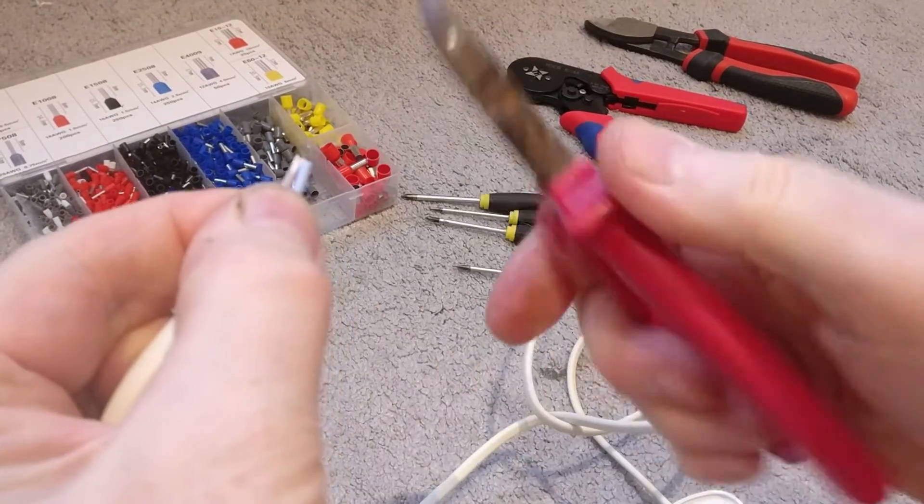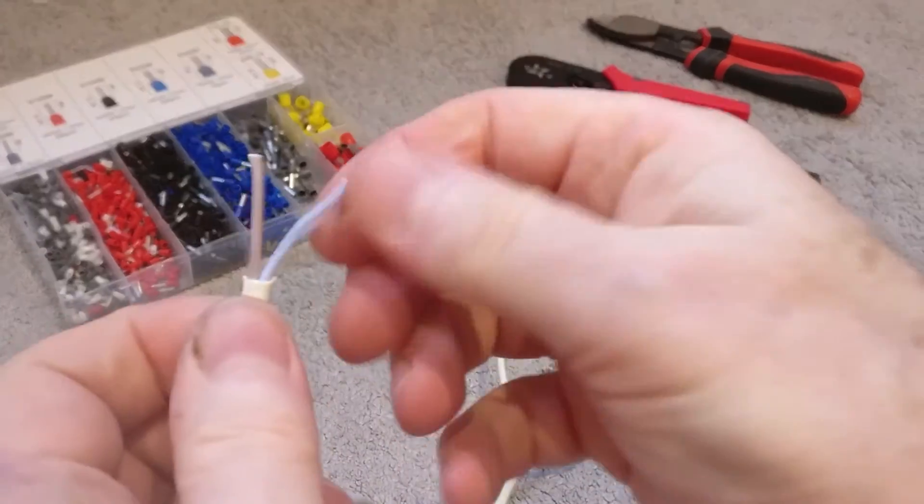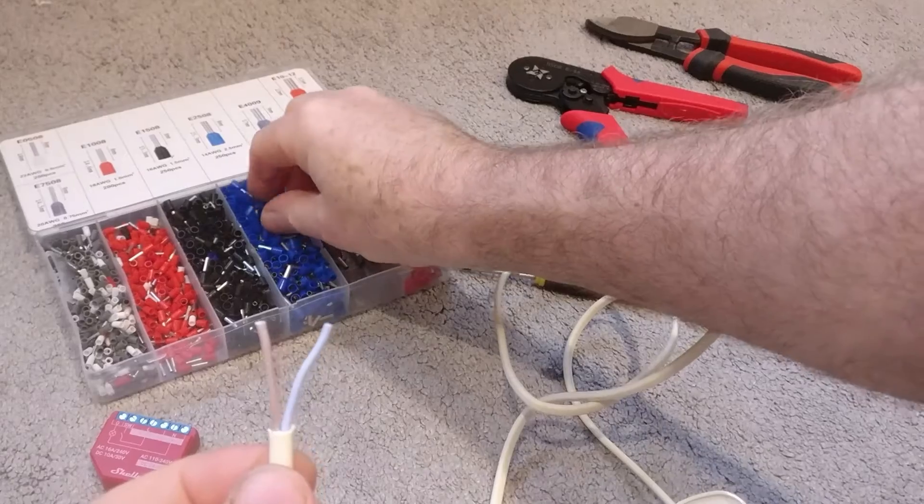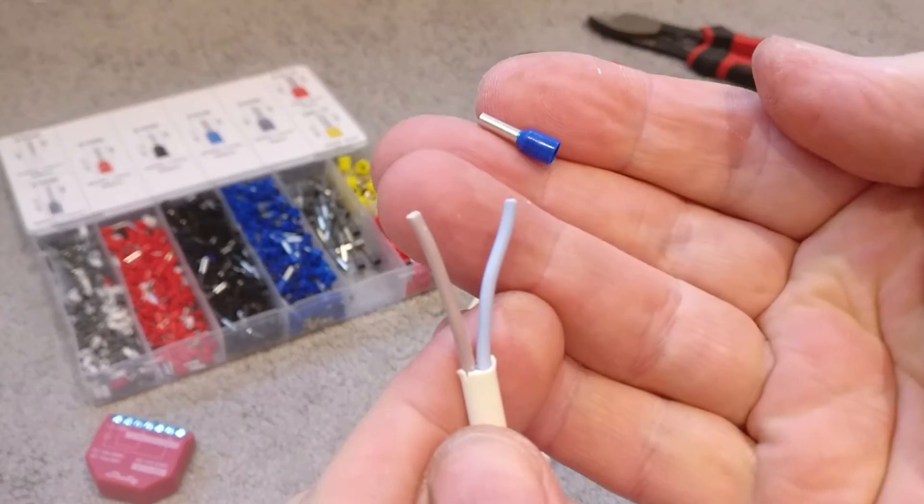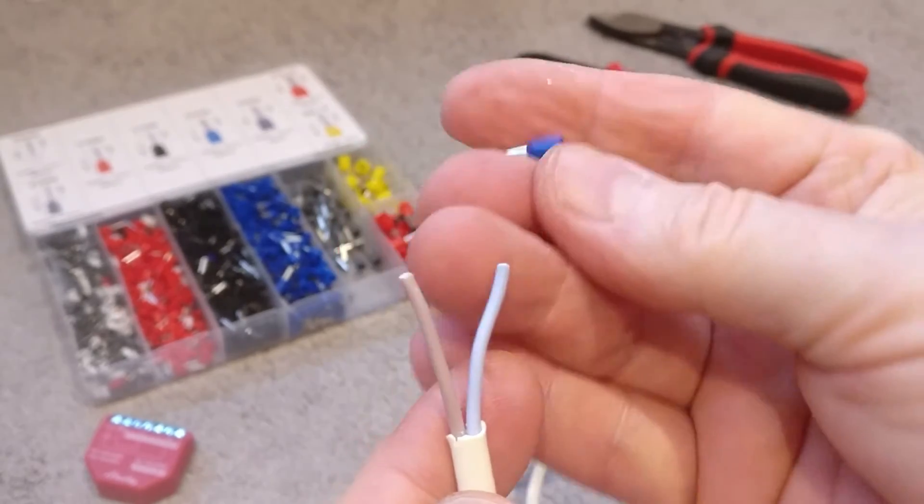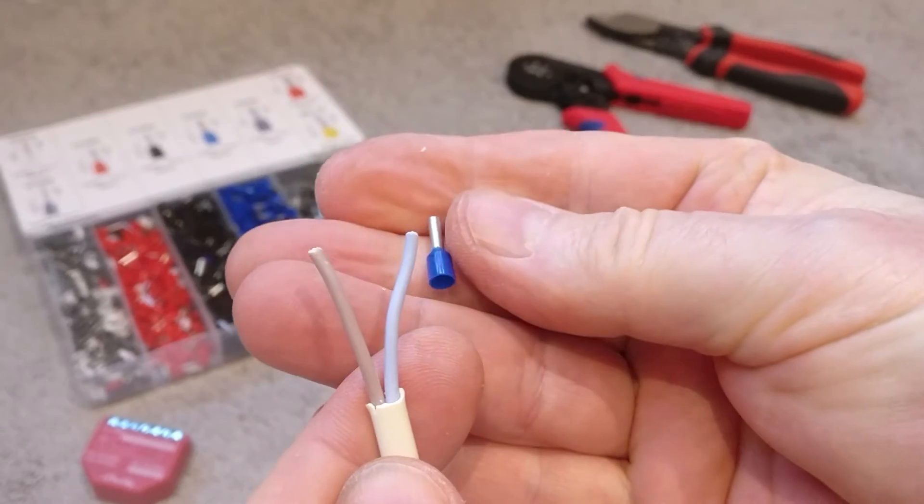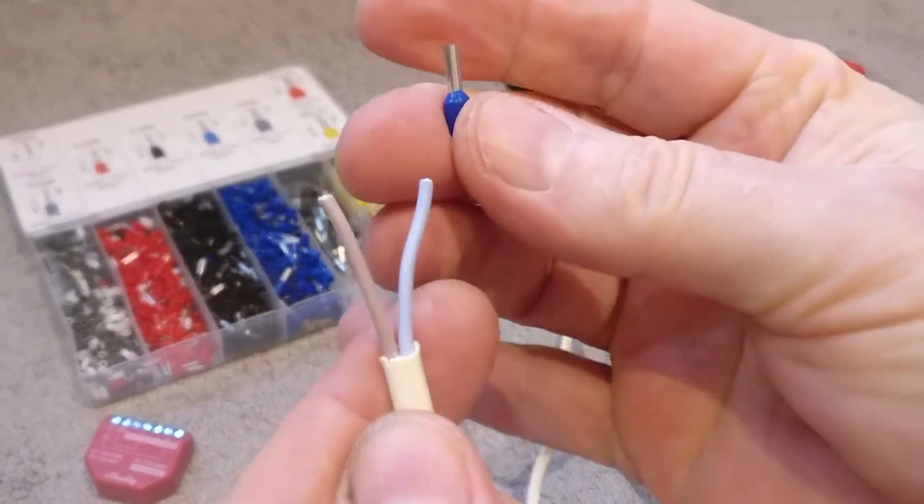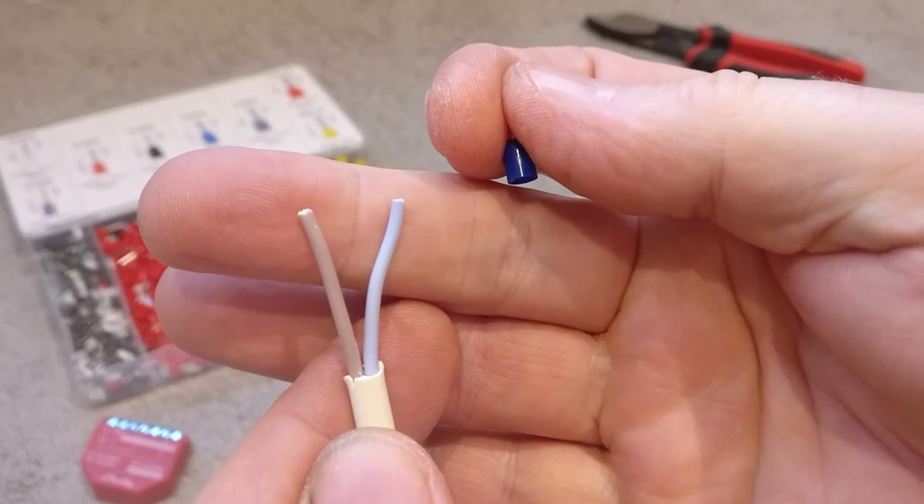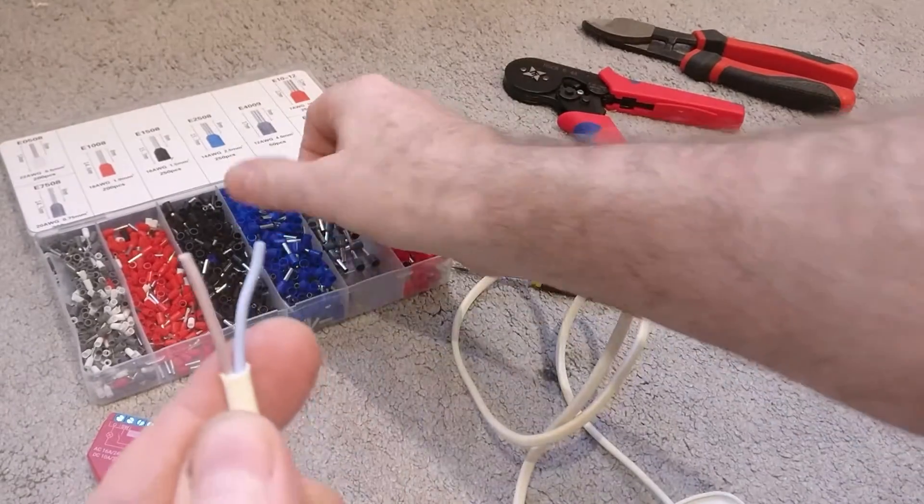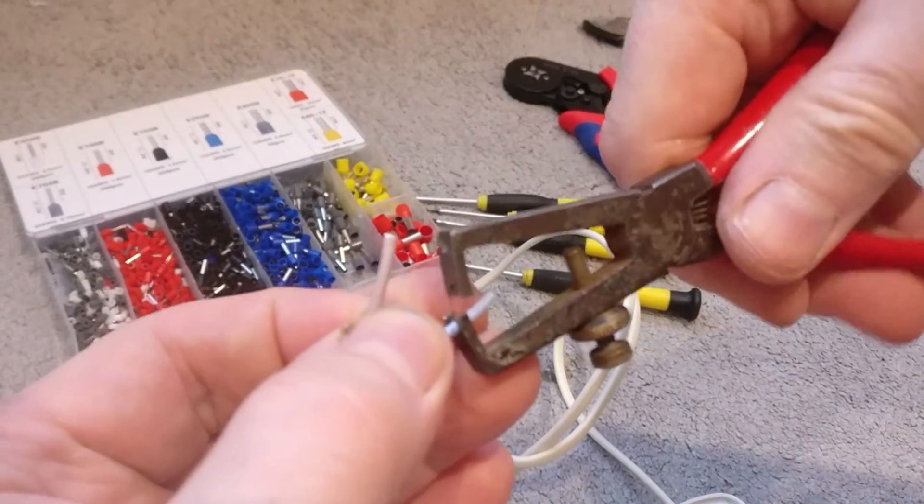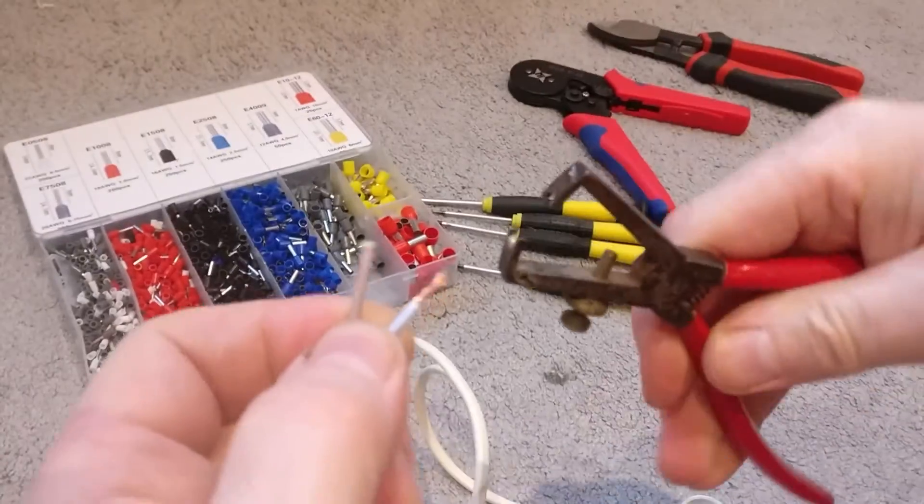Chop these down just to a smaller workable length. What I'm going to do is use these ferrules. If you've seen some of my earlier videos you'd have seen me use ferrules. Ferrules provide a much more secure and mechanical connection, much much safer in my opinion. If you've not seen my other videos have a look, I'd really recommend it. Ferrules are definitely the way forward. So first thing to do is just strip back so you can expose the copper core. Give yourself maybe a centimeter or so.